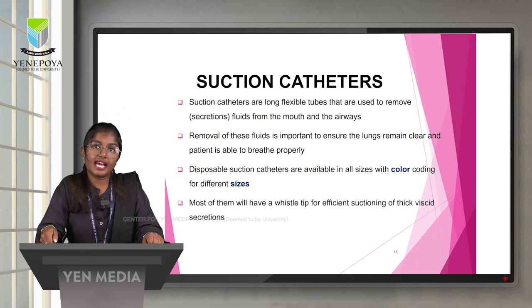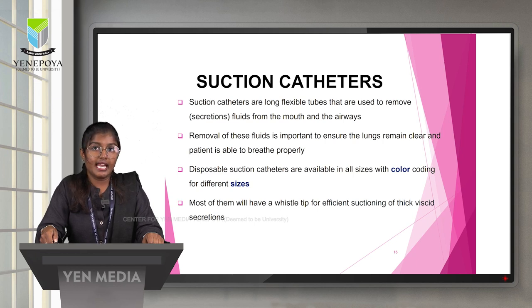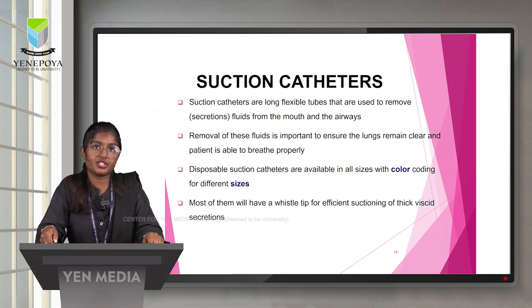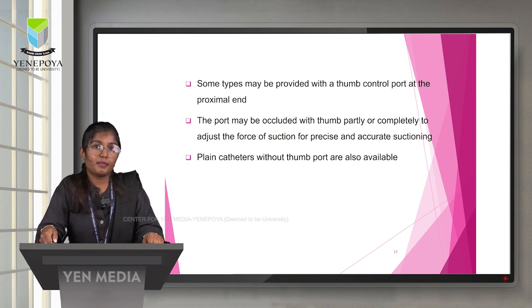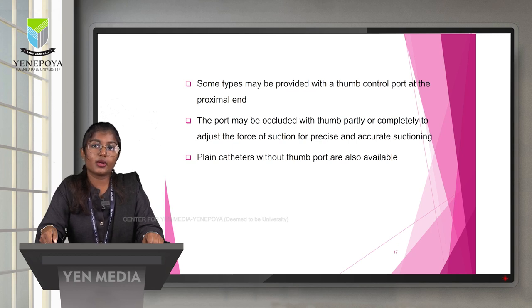Suction catheters are long flexible tubes used to remove secretions and fluids from the mouth and airways. Removal of these fluids is important to ensure the lungs remain clear and the patient is able to breathe properly. Disposable suction catheters are available in all sizes with color coding. Most have a whistle tip for efficient suctioning of thick viscous secretions. Some are provided with a thumb control port at the proximal end to adjust the force of suction partially or completely. Plain catheters without a thumb port are also available.